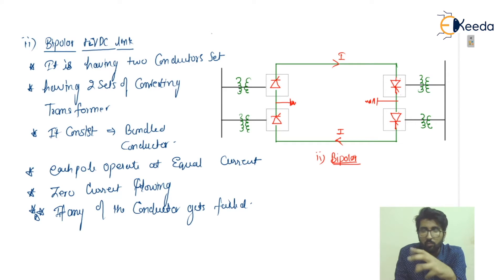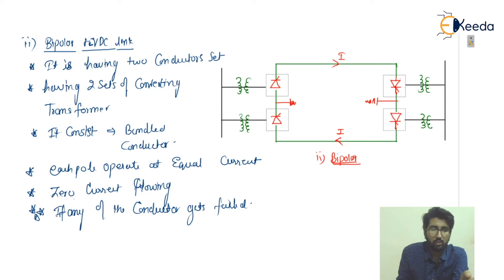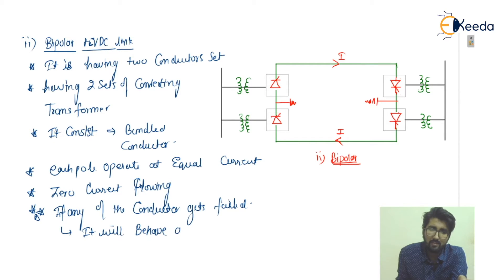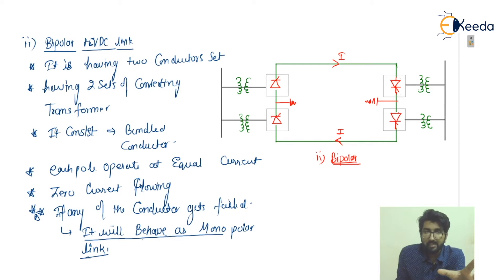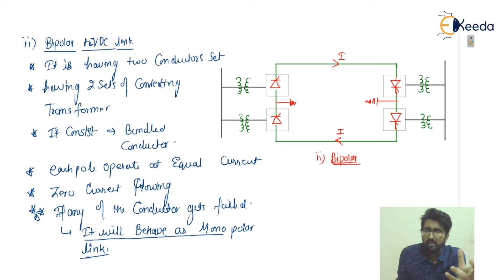So if any conductor gets failed, it will behave as a monopolar link. To summarize the bipolar link: it has two conductor sets each with two converting transformers, zero ground return under normal conditions, and each pole operates at equal current. If a conductor fails due to a fault or abnormal condition, it behaves as a monopolar link.